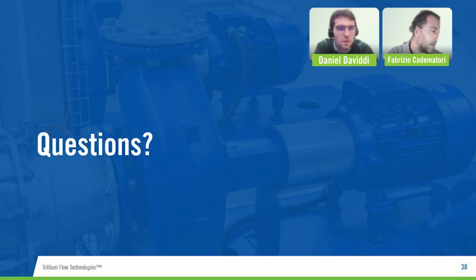I think we can close the meeting with the last question because it is very interesting, from David. In your experience, when vane pass is the dominant vibration on the pump, what is the main cause? NPSH required versus NPSH available, wrong hydraulic analysis? So, which is the design or operational condition that can increase the blade or vane pass? Fabrizio, do you want to answer? Okay. My first answer is a joke. Our fluid dynamic analysts are very good, so they design a very good impeller without blade pass problems. But it is a joke.